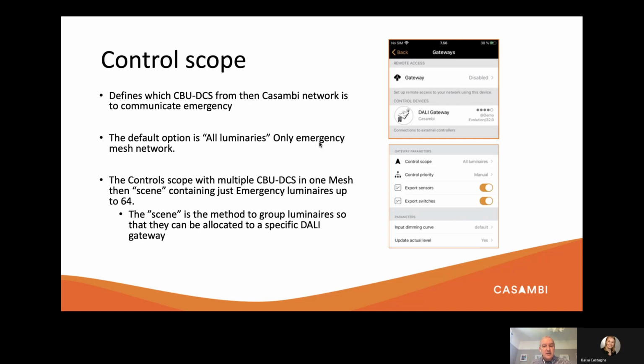If all the luminaires in the network are emergency only, then you choose all luminaires in the menu, in the gateway parameter menu. That means all the emergency Casambi enabled devices connected and communicating back to the gateway are presented back to the DALI controller as emergency devices and nothing else.